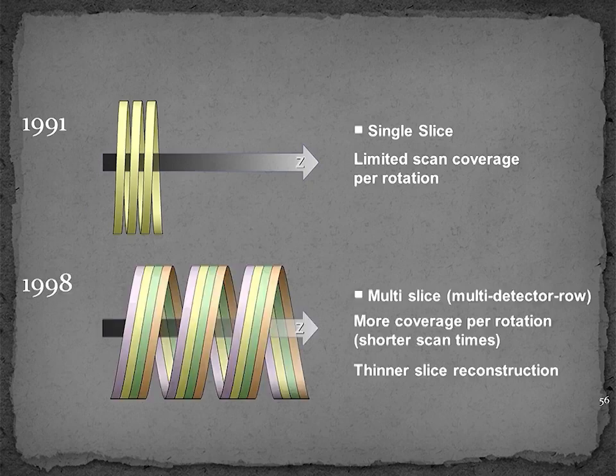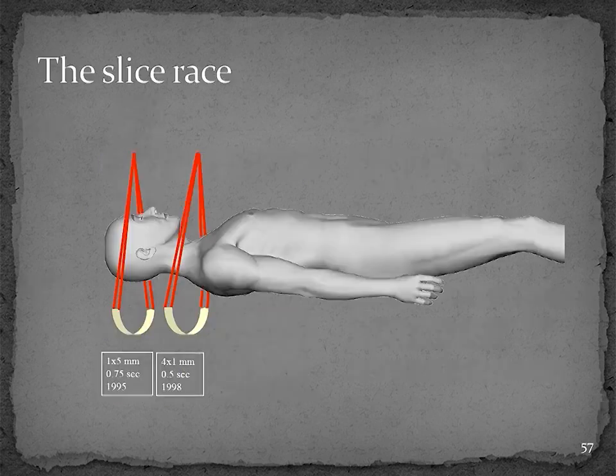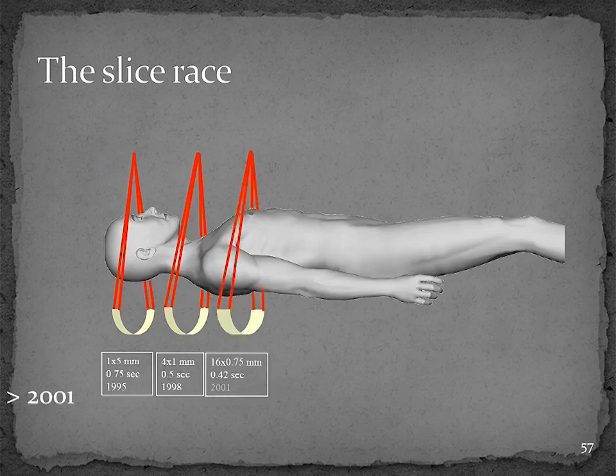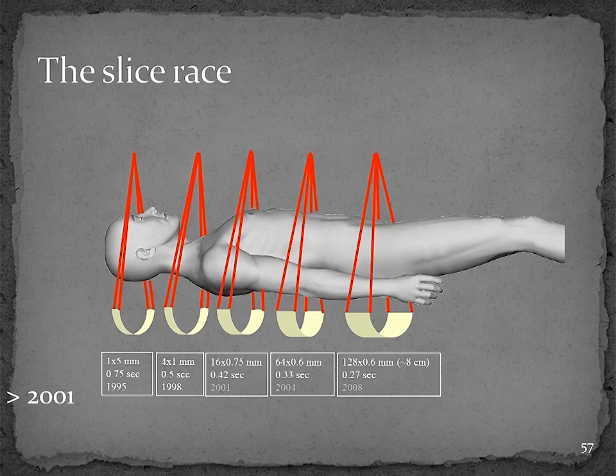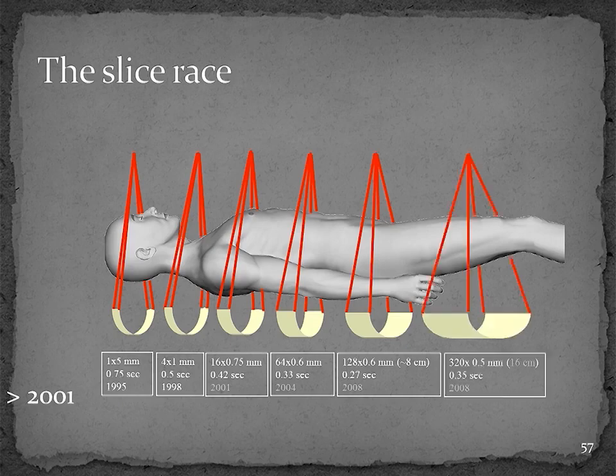In 1998, scan speed was dramatically improved by having multiple rows of detectors. This began the era of multi-slice or multi-detector row CT and initiated what became known as the slice race, where manufacturers kept adding more and more detector rows and data channels until now we have scanners with 320 data channels and half millimeter thickness that can cover 16 centimeters of the patient along the Z-axis in one gantry rotation.